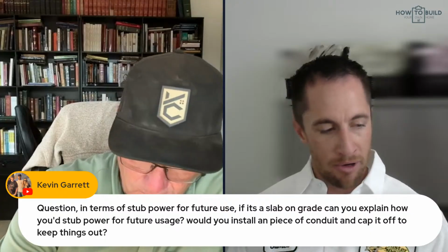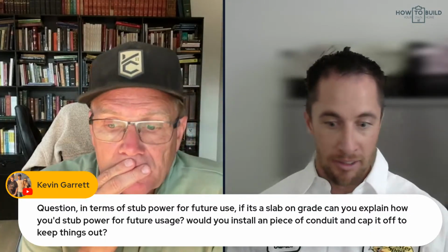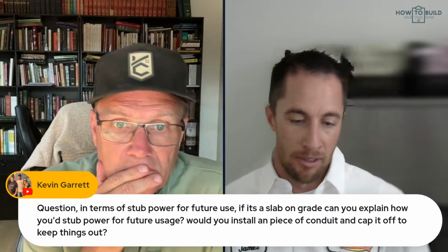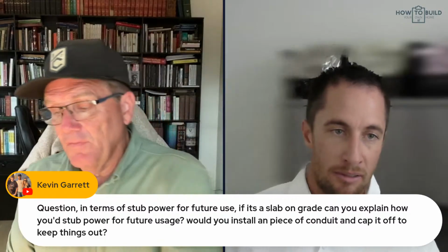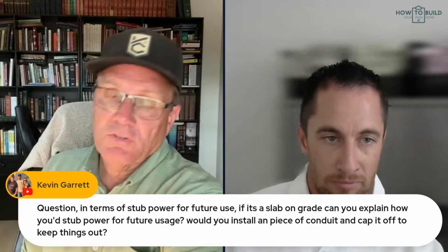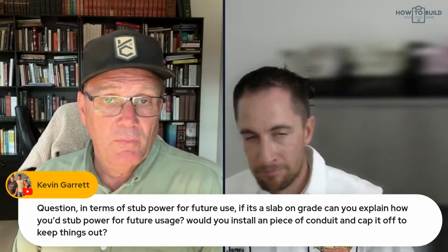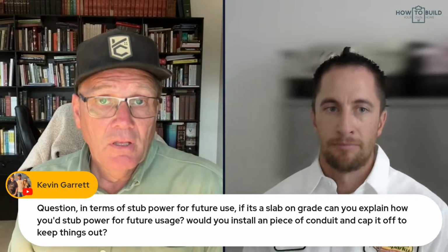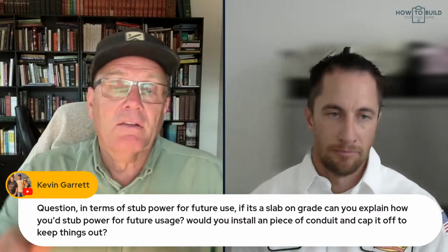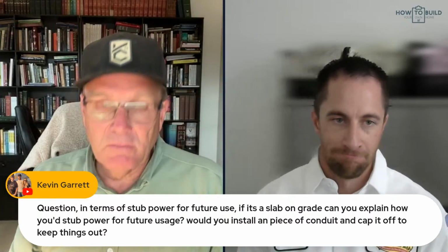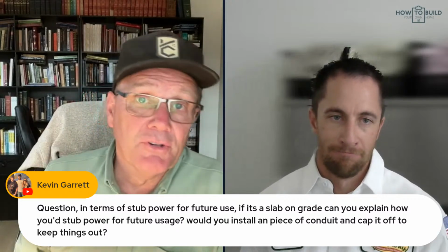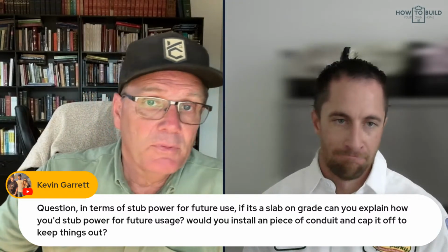If you don't know exactly where, and you're thinking maybe here or maybe here, then stub to both locations and have it there. And if you put conduit into a slab, make sure it's below the dirt, below the rebar, not on top of it. If you do that wrong, you'll get a crack in your foundation. By code, it has to be below the rebar and in the dirt. Just do that and you'll be fine.